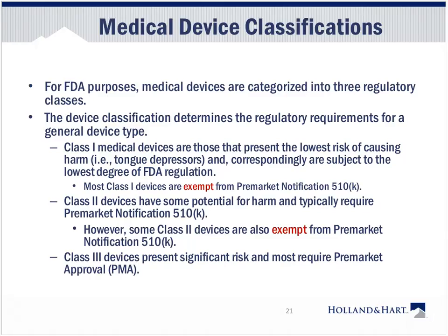Class 2 devices have some potential of harm and typically require a pre-market notification, and you'll often see it referred to as 510K because that's the section of the code that it's in. Some Class 2 devices are also exempt from pre-market notification, and we're going to run through an example, so I hope that this will become clearer. And then Class 3 devices present significant risk, and most require pre-market approval. Premarket approval is different from premarket notification. We're going to get to that, but it is just a jump in terms of what has to be proved to the FDA about the safety and effectiveness of a product.